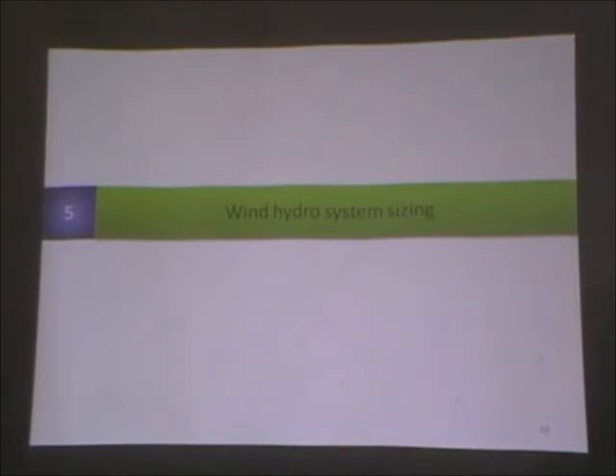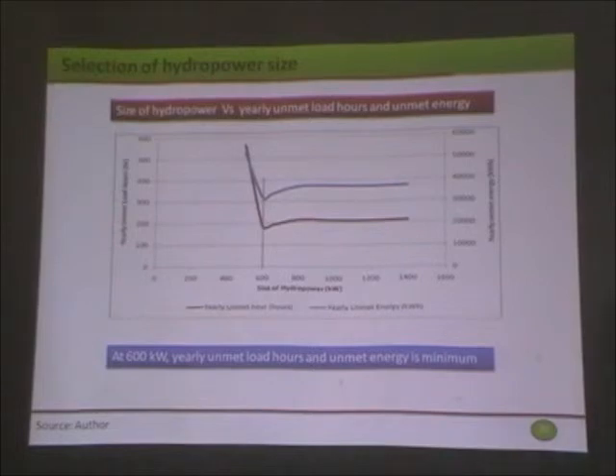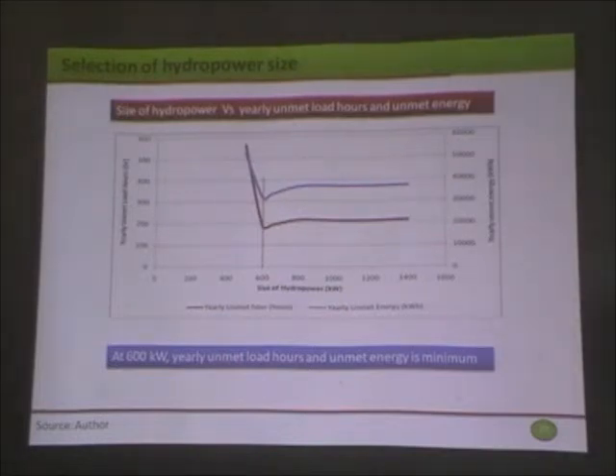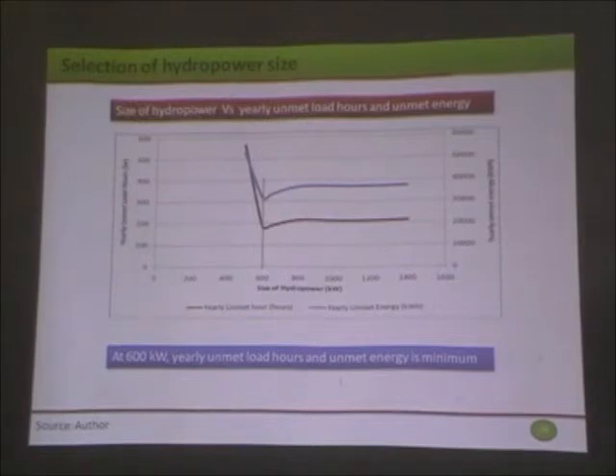Now let's switch to wind-hydro system sizing. I will show the main slides only. For selection of hydropower size, the Y-axis shows yearly unmet load hours where demand is greater than supply, and the X-axis shows different sizes of hydropower. The minimum yearly unmet load occurs when the hydropower size is 600 kilowatt, related to the demand curve of the area shown earlier. For my calculations, I chose 650 kilowatt as the optimum size.